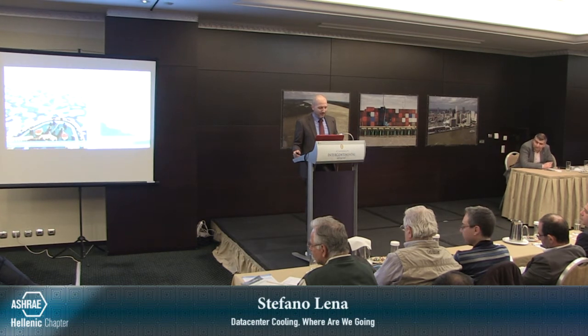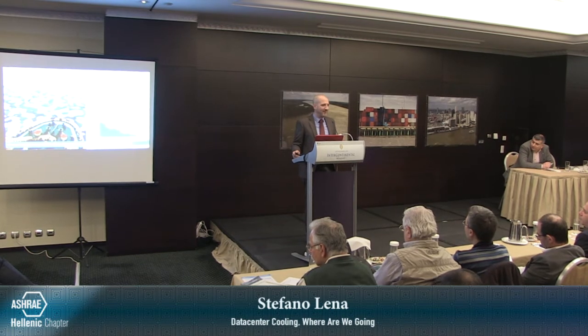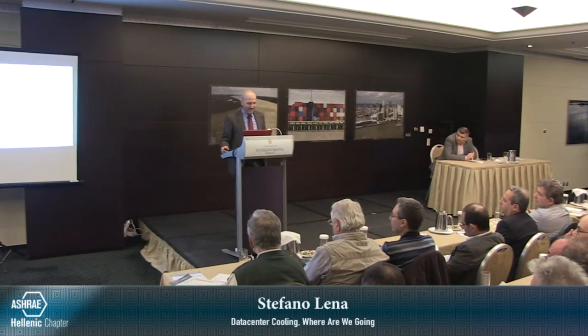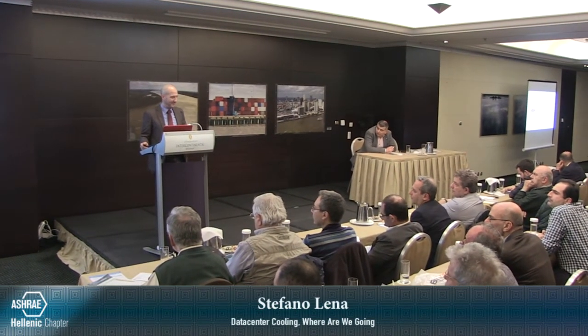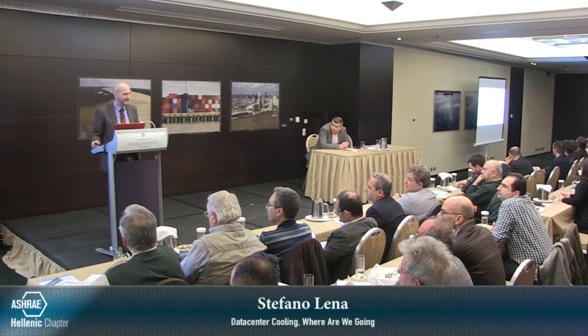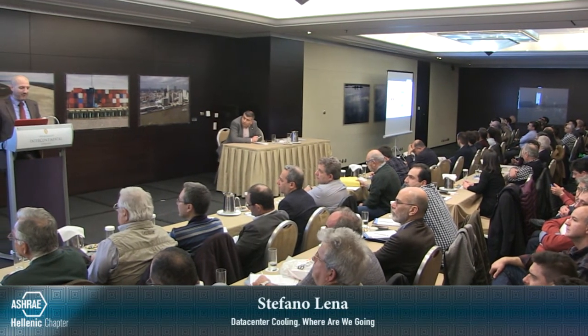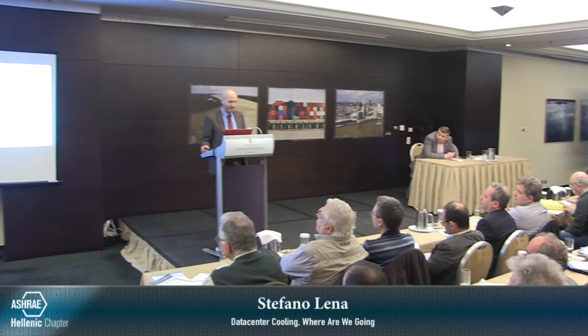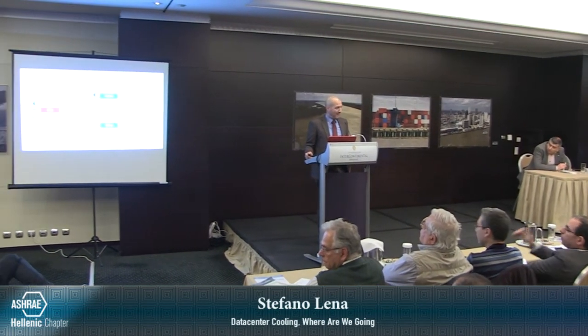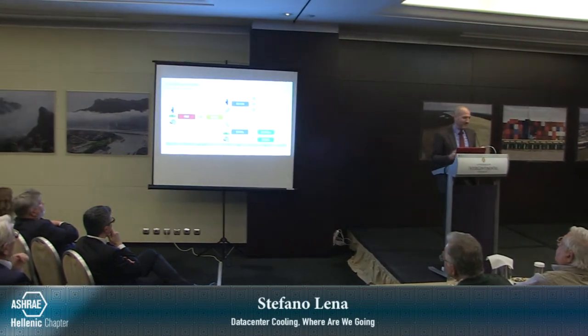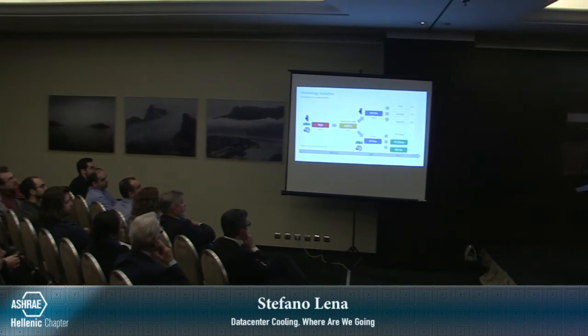From a historical perspective, once upon a time there was just one refrigerant, good for all. Today it is not anymore. This is a short storyline of what happened in the world of refrigerants. The first fork happened in 2005, when two types of refrigerant were established: R410A for the scroll compressor and R134A for the bigger compressors, screw and variable speed compressors. But today we are experiencing multiple forks because the trend is looking for lower GWP refrigerants.